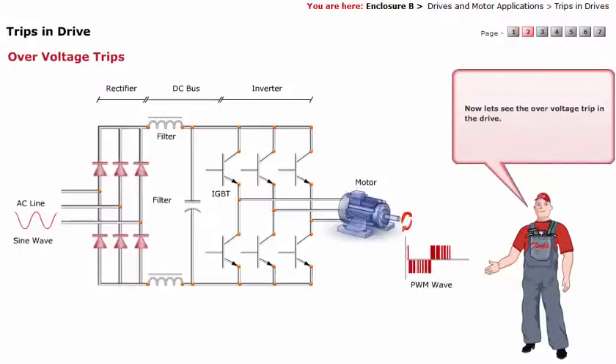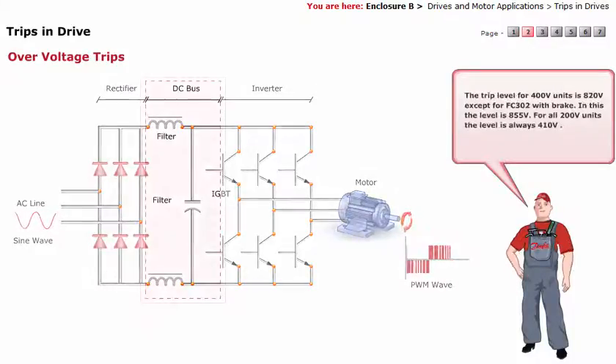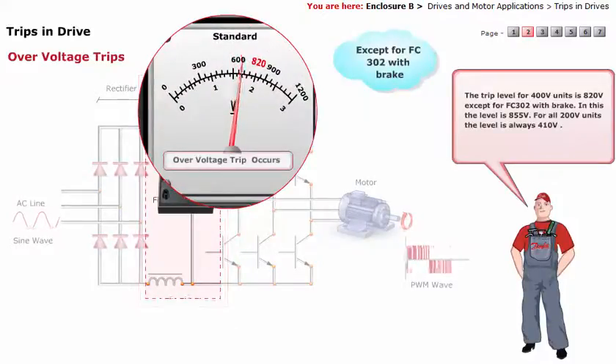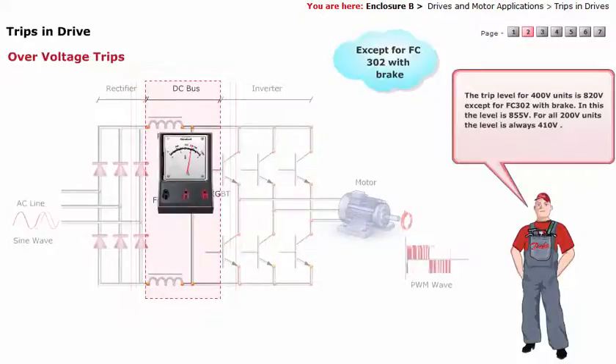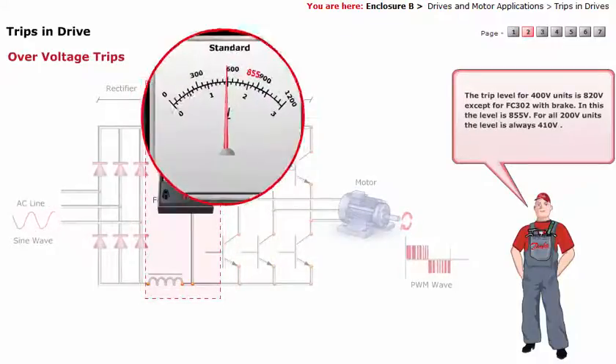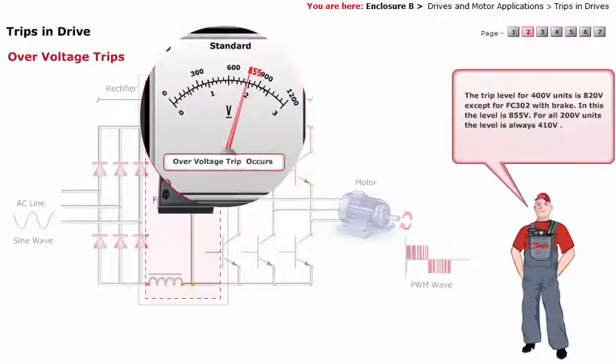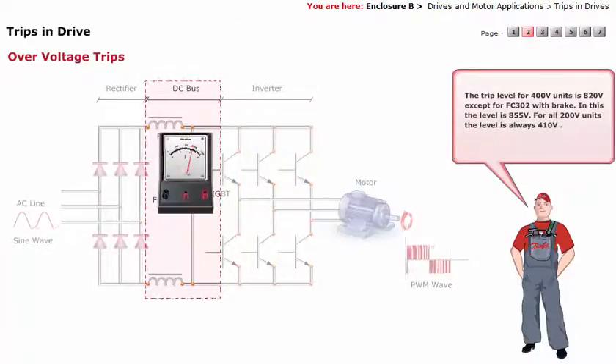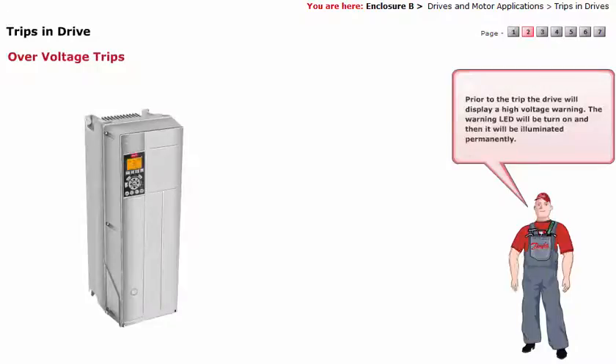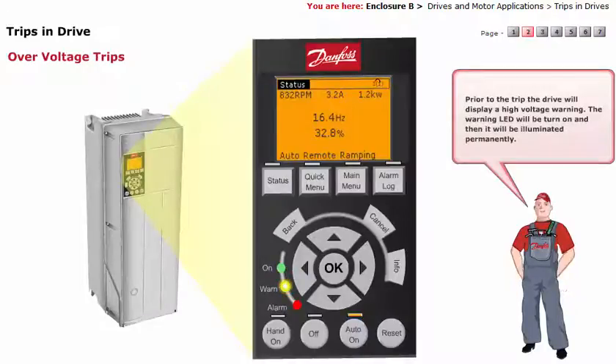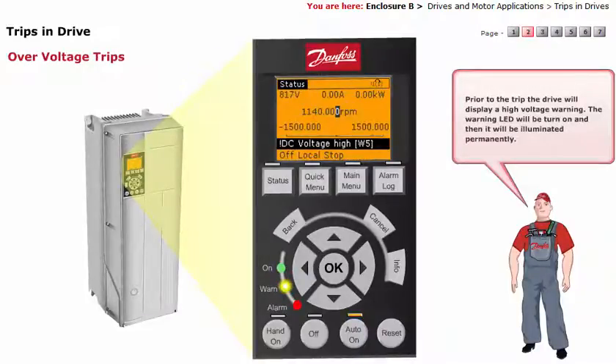Now let's see the over voltage trip in the drive. The trip level for 400-volt units is 820 volts, except for FC302 with brake, where the level is 855 volts. For all 200-volt units, the level is always 410 volts. Prior to the trip, the drive will display a high voltage warning, and the warning LED will be turned on and then illuminated permanently.